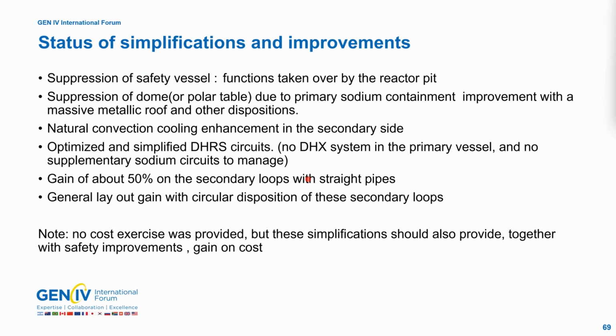We have a good natural convection in the secondary side. We have optimized and simplified the DHRS circuit. There is no more DHX system in the primary vessel, and there are no supplementary sodium circuits to manage. We have a gain of about 50% on the secondary loop with straight pipes. And we have a general layout gain with a circular disposition of the secondary loops around the primary circuits. We can note that no cost exercise was provided during the SFR Smart project, but all the simplification that gives improvement for safety also gives improvement in terms of the cost of the reactor.